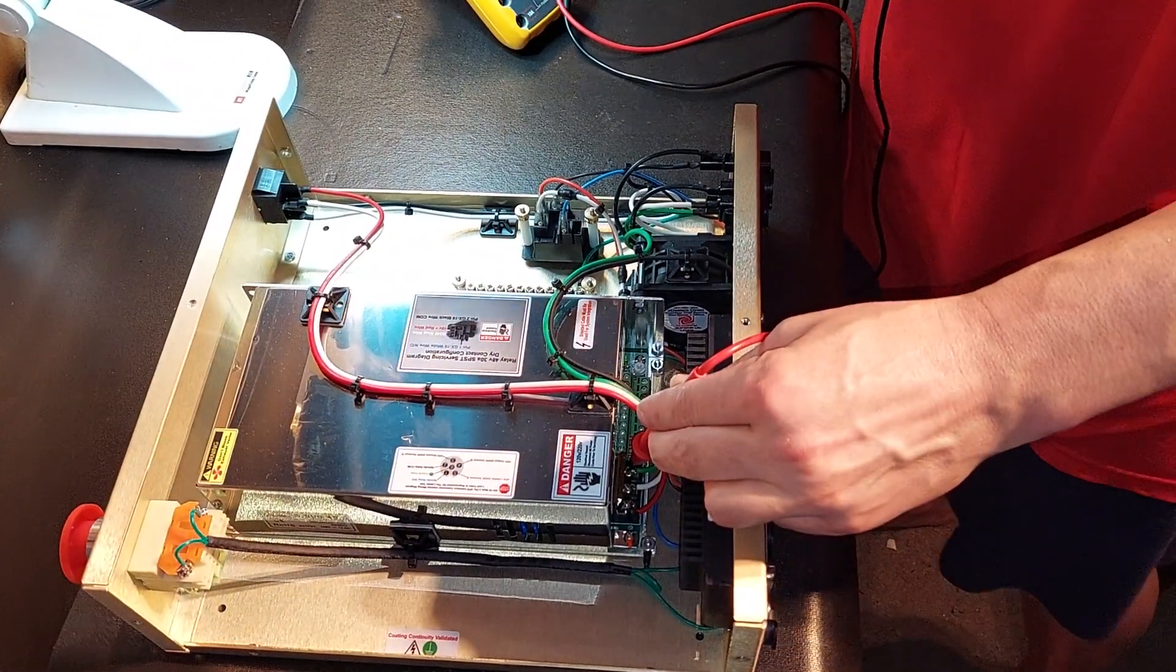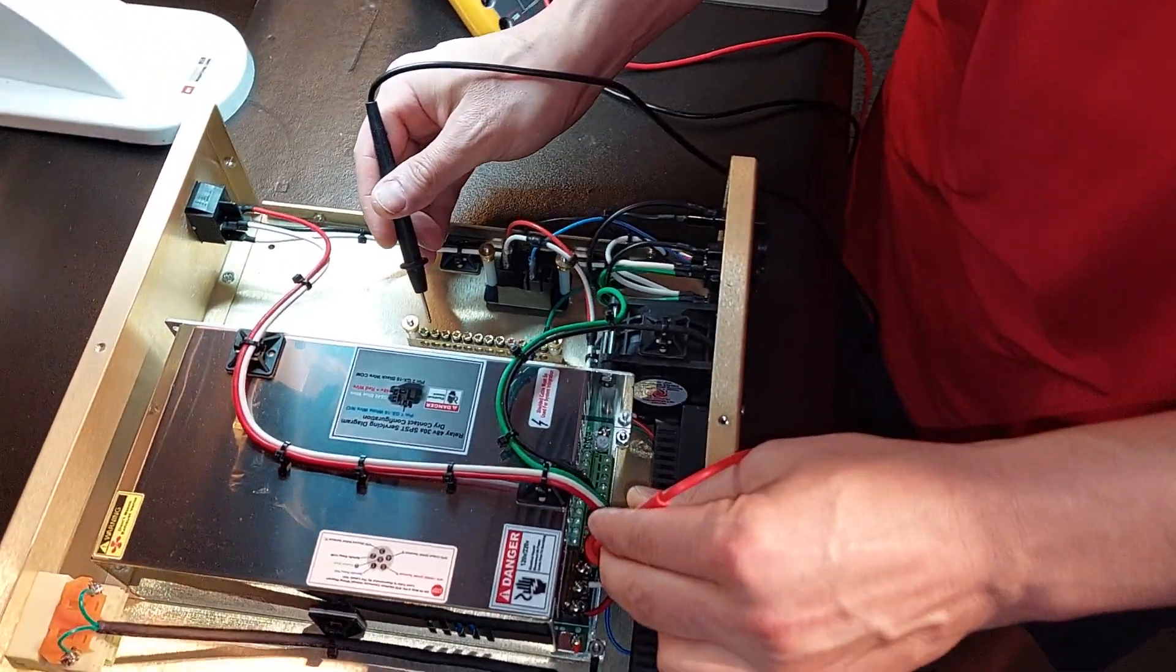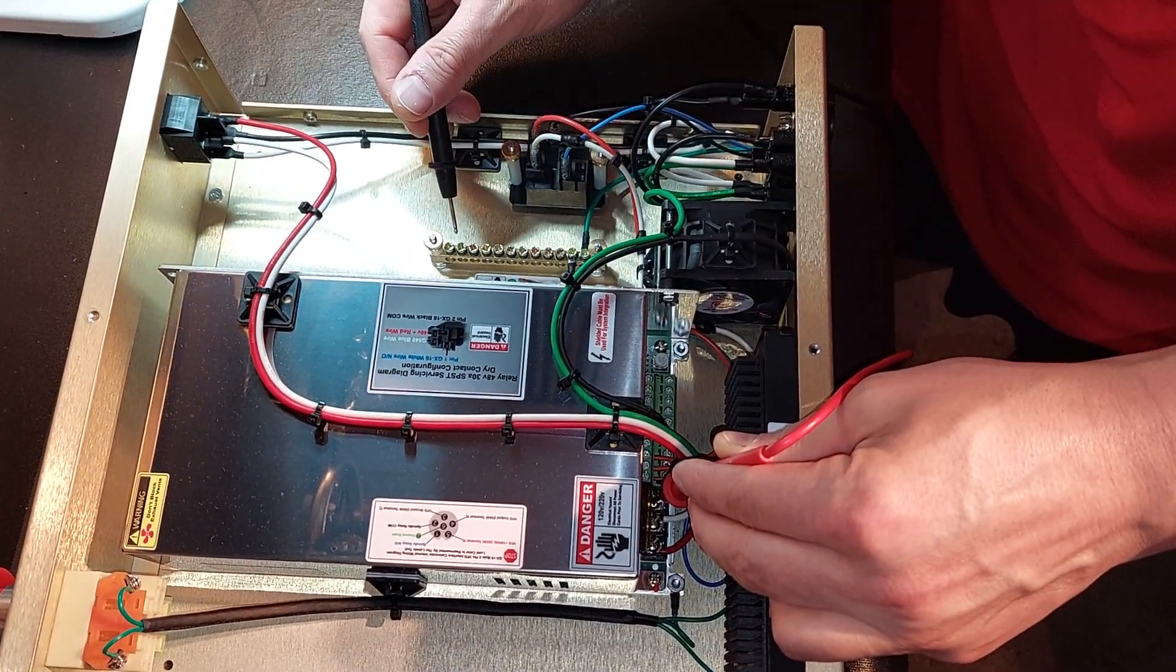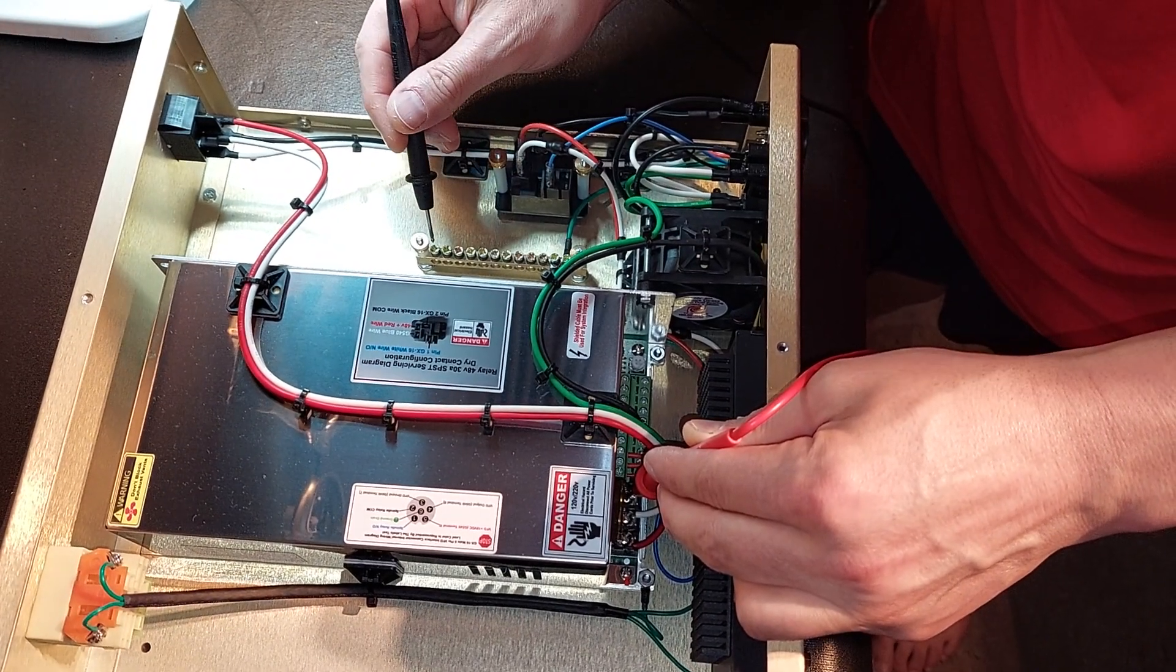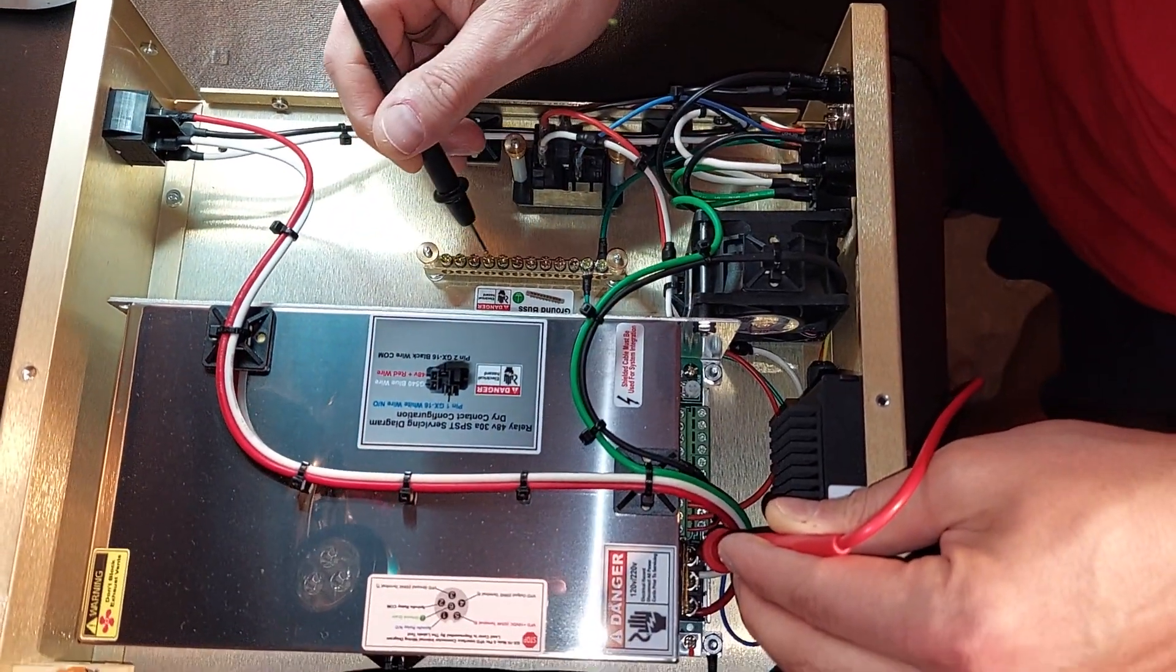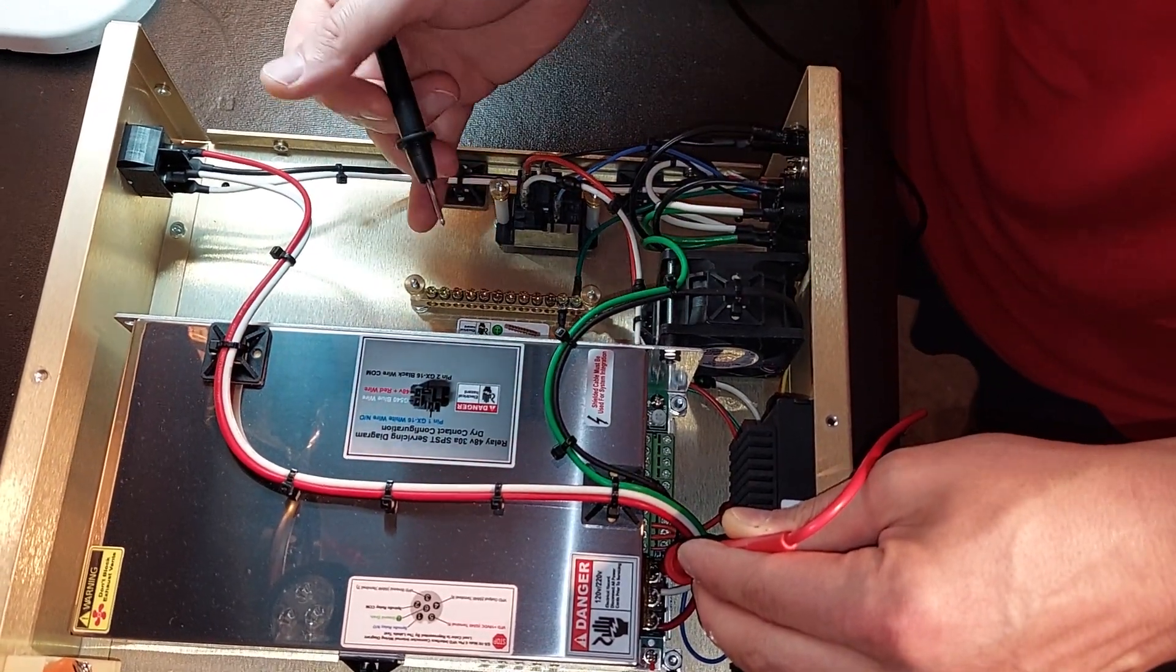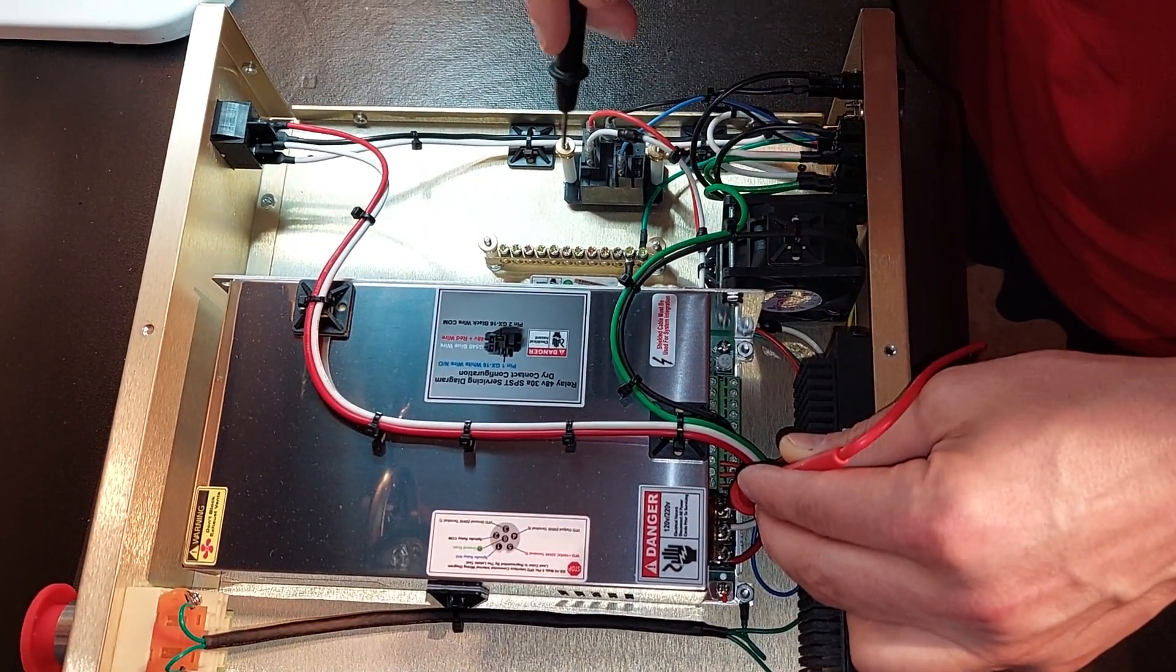Understanding this is imperative. A lot of guys get lost in detail in what they think they understand with a star point ground, that a bus bar is used for everything. A bus bar is really only used for multiple accessories to ground from at one central point. The idea of a bus bar is so that you have a bar coming in with a terminal, or in this case, the chassis grounded, and then through conduction you've got the bus bar grounded. That means whatever is attached to any of these terminals is going to be a ground point. So this would be one way to look at the version of a star point ground, but in general practice when you're building your system, you want every ground for the system to be interconnected.